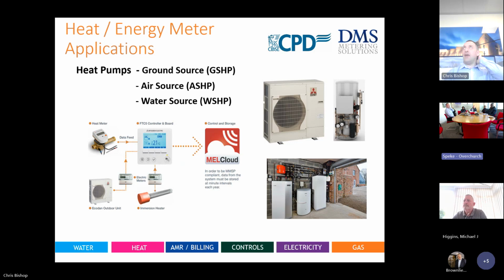And a big thing now that is everywhere in the industry is ground source, air source and water source heat pumps. On every design that we're seeing now, you could say it's changing how HIUs are supplied in applications. It's becoming a heat pump. The main plant room application might not be a gas-fired boiler anymore because they don't want to do that, and that's quite a common thing now. But a heat pump would solve that particular issue. So heat pumps are being seen more as a design factor for the main plant room applications for certain buildings, and then the apartments would still have the heat meters installed.